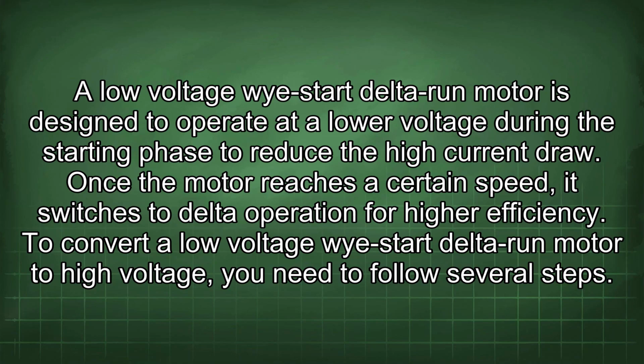A low-voltage Wye-Start delta run motor is designed to operate at a lower voltage during the starting phase to reduce the high current draw. Once the motor reaches a certain speed, it switches to delta operation for higher efficiency. To convert a low-voltage Wye-Start delta run motor to high voltage, you need to follow several steps.